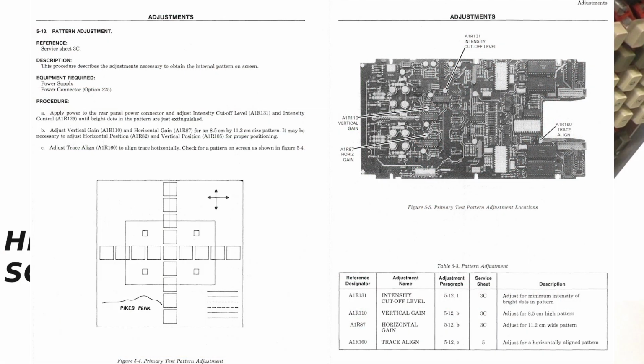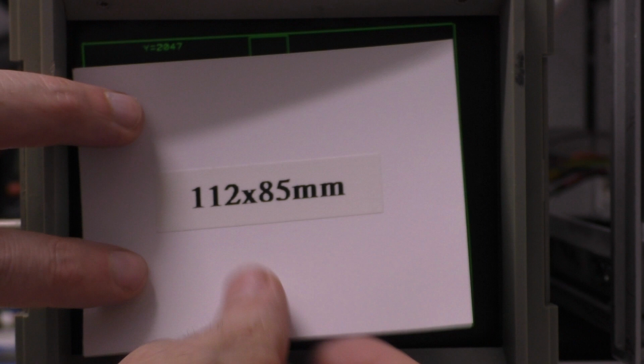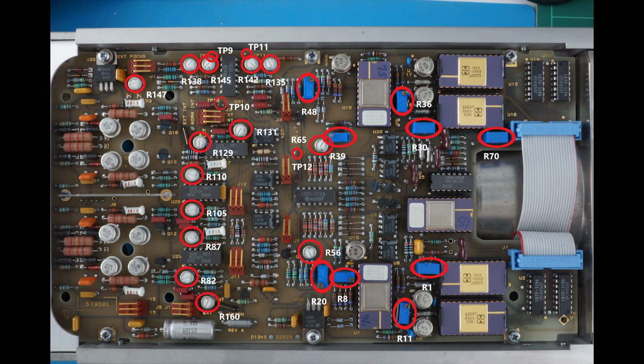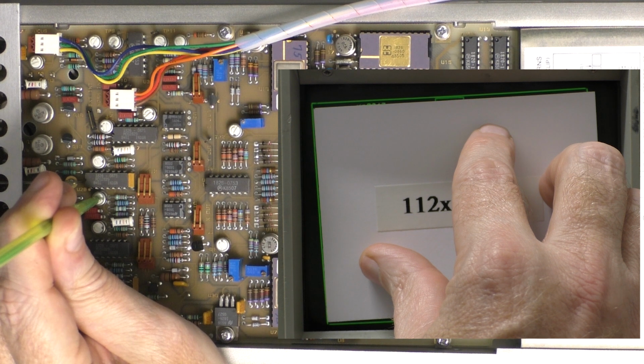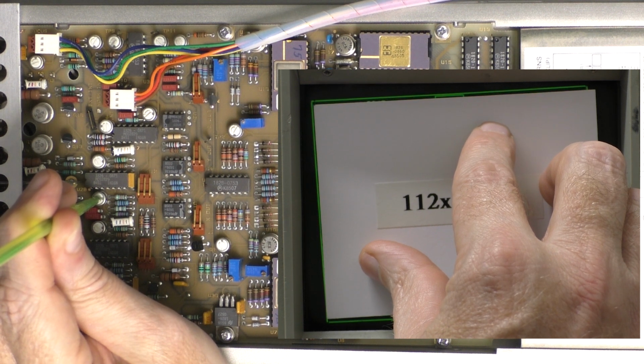Moving on to pattern adjustment. 5-13-B, vertical and horizontal gain. These adjust the size of the displayed image. Create a cardboard template measuring 112 mm by 85 mm. Locate R110 on the A1 board. This is the vertical gain. Place the template over the screen. Adjust R110 until the height of the test pattern is just obscured by the template.